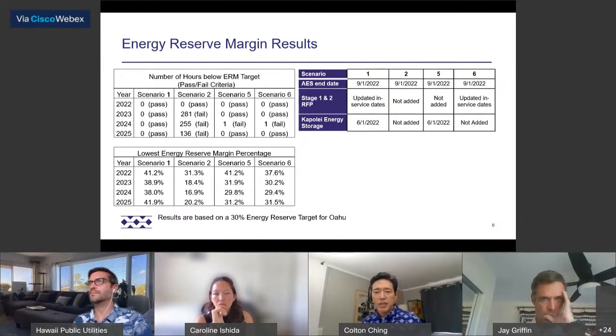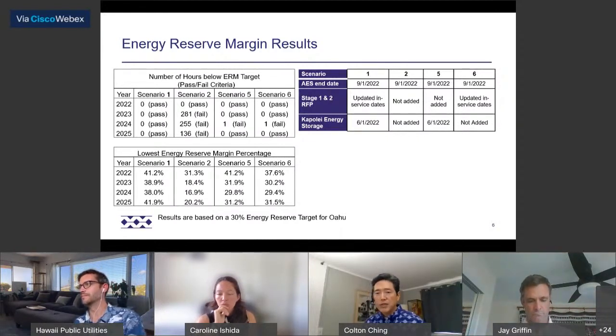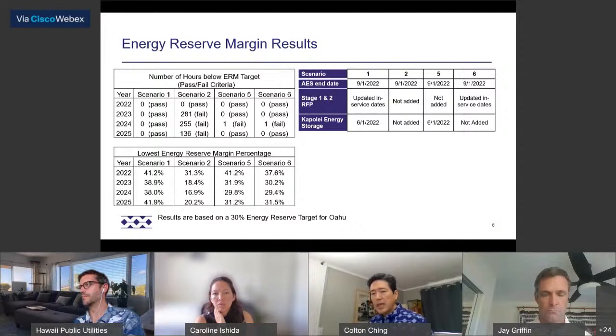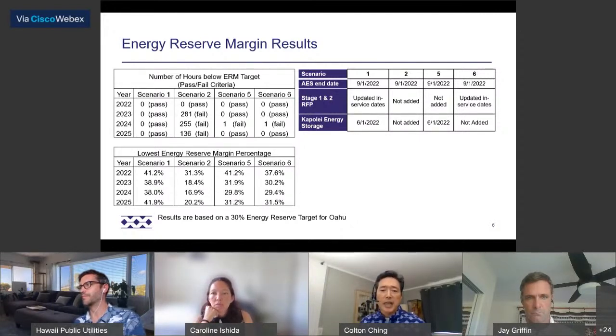For Oahu, we use a reserve margin of 30% to account for what's not included within our ERM calculation in terms of uncertainty. There's uncertainty of load - is our forecast for the load for that hour spot on? It may be off, so that reserve margin accounts for variability in that. It accounts for, as Derek spoke about earlier, unscheduled outages, whether it's a maintenance outage or a forced outage rate of a firm generating unit. It also accounts to a lesser extent for the remaining uncertainty of variable generation performance in that hour.